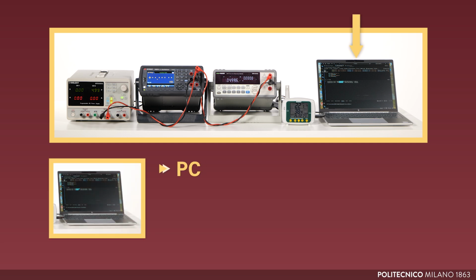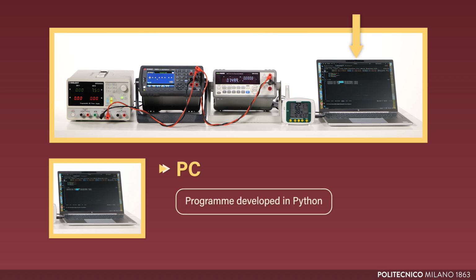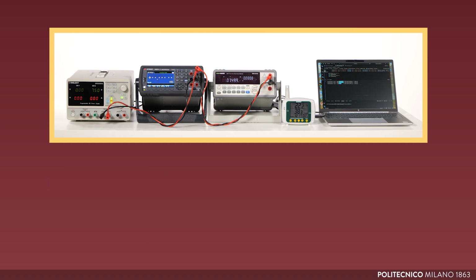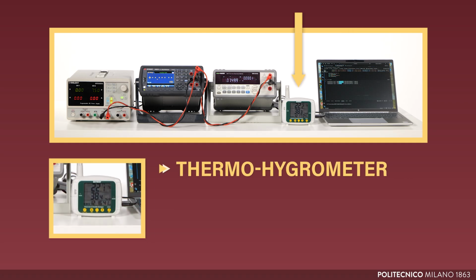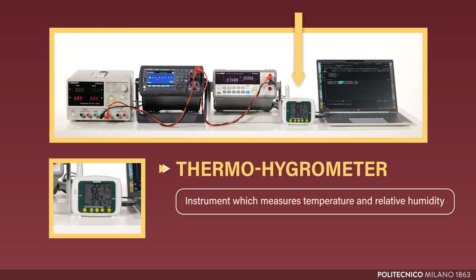Next to the instruments, you can see a PC that we use to manage the various calibration steps automatically by means of a program developed in Python. This is common practice in the most modern and well-equipped calibration laboratories. You can also see a thermohygrometer, that is an instrument which measures temperature and relative humidity so that we know the conditions under which the calibration is carried out.